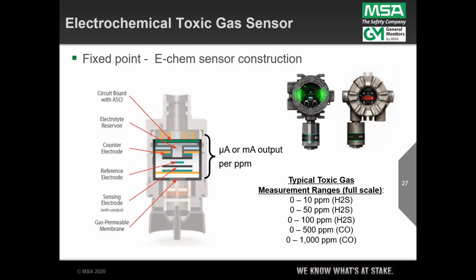And so our engineers vary the electrolytic fluid and the electrode materials to provide specific response to different gases. So even though they're all built in a very similar way, it's the chemistry within that is very specialized to provide that high accuracy measurement capability to the different gases shown in the lower right-hand corner. H2S, carbon monoxide, we have chlorine, we have a full range of gases.